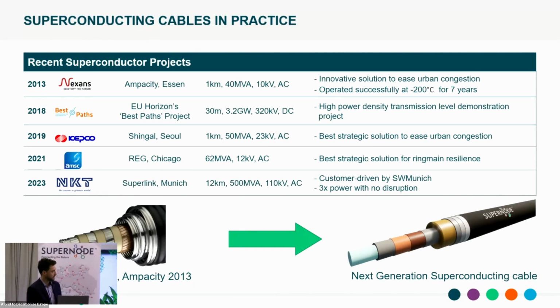Lastly, I'll highlight the NKT project, the Superlink project in Munich, on track to be delivered in 2027. It really signals a step change in utility acceptance for this type of technology, and in the applicability and functionality of the technology. It's a 12 kilometer long superconducting cable system under the city of Munich, 500 megawatts in rating, really getting into transmission levels of power, operating at 110 kV.